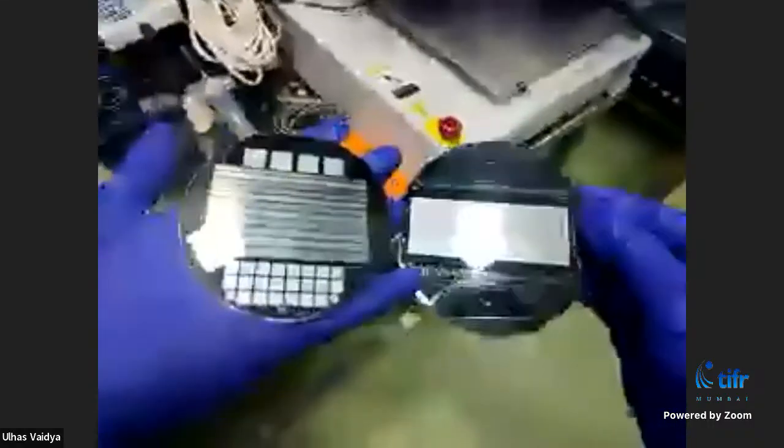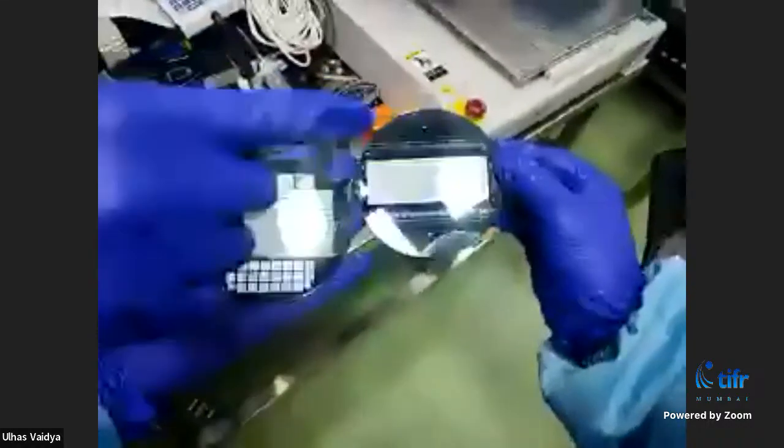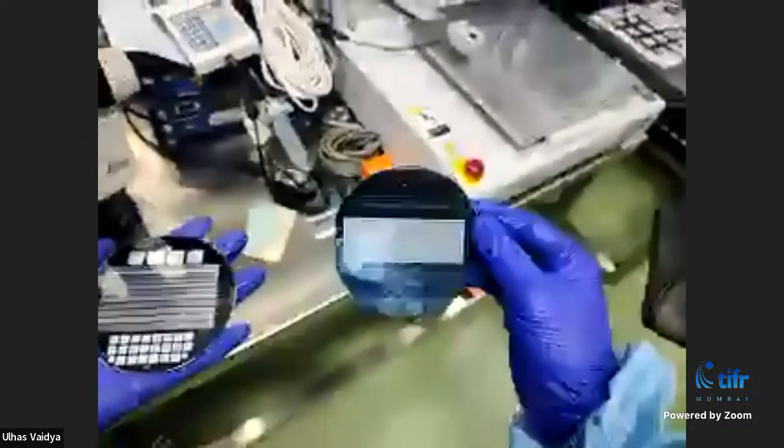There are two detectors now. You can see them. Can I add one? Yeah, please go ahead. We have 11 sets there, which are different width and pitch. And this one has only one set. Each has 1024 strips with 50 micron width and 75 micron pitch. That is the difference between these. Yeah, so 1024 strips in this little detector.